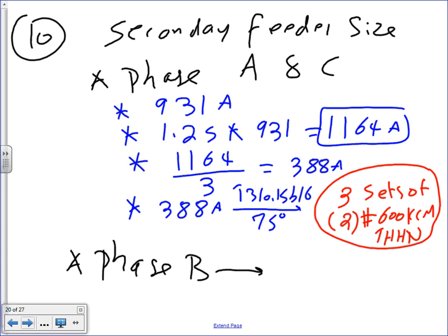Why did I parallel here? Because I don't think there is any conductor that can give you that much in a single 1000 kcmil. You have to go to bus duct almost. What's the largest they can get amp wise? 605, something like this. 665 is the largest. So even if you want to, you can't pull it. Okay, phase B. I'm going to give myself room. You guys have room, so you can do phase B.